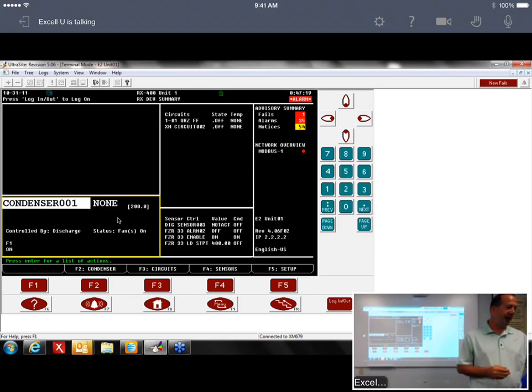The reason for that is we had a developer early on at CPC that thought the networks were backwards in the way that they had the polarity. So he decided, hey, we're going to do it this way. It was fine when we had all of our own case controls, our own boards, all that stuff. When we started integrating products that used the same protocols on the network, it became an issue, and we had to reverse the polarity. So it's an idiosyncrasy of CPC.